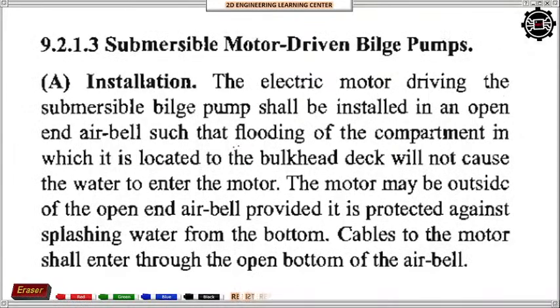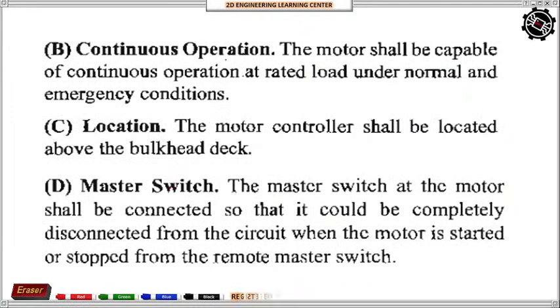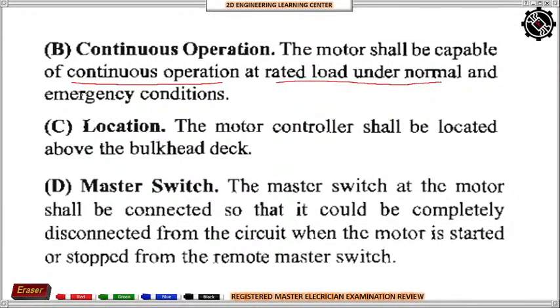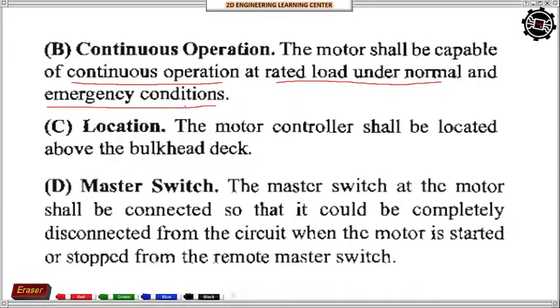Okay. So submersible motor-driven bilge pump, no? So ito katulad pa din yung kanyang provisions, no? So it must be installed in an open end air-bell. Such flooding, no? Kapag nag-flooding, hindi siya mag-stop ng pag-work or pag-gana. Okay, so continuous operation. The motor shall be capable of continuous operation at rated load under normal and emergency condition. Hindi siya talaga nag-stop even if the electrical system is just powered by the emergency system.